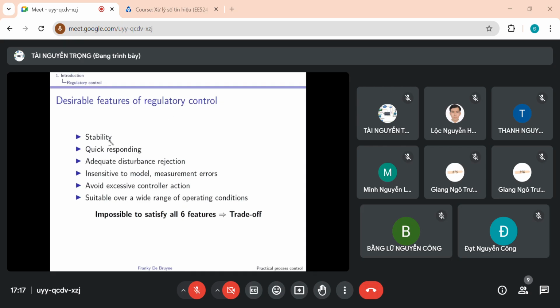These are the desirable features for regulatory control. The first feature is not desirable, it is necessary. We have to impose the stability of the closed loop system. The second feature has to do with tracking. We want PV to go to its set point as fast as possible. So when there is a closed loop set point change, you have indices like settling time, rise time, and so on. Of course, you have to have an adequate disturbance rejection, and this you can see in terms of variation around the set point. You have to be insensitive to model and measurement noise. So this means that if the process, for instance, changes a bit, the process controller should still be able to control the system with adequate performance. And this is sometimes called robustness.